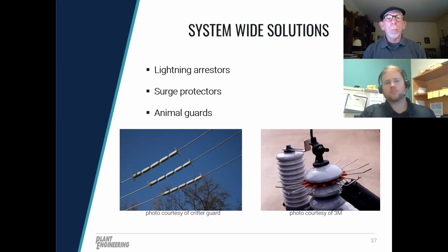This slide goes over some grid level solutions. These are really out of our control. They will be implemented by the power utility, typically on the distribution lines. Some examples include arrestors, surge protectors, and even something very simple, animal guards. Keep in mind that momentary interruptions may be more common in the summer because animals are more active. Storms are also more common in the summer, the storm season, hurricane season. And then also tree growth. Vegetation trimming may be a relatively easy fix compared to some other more high tech or more expensive options.